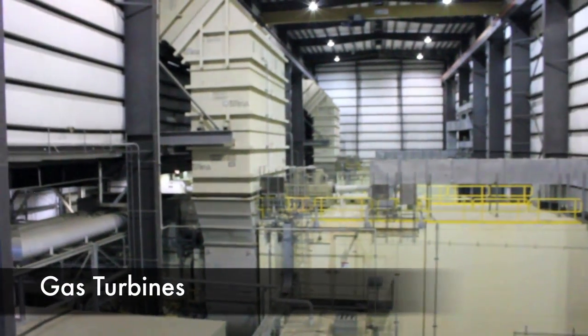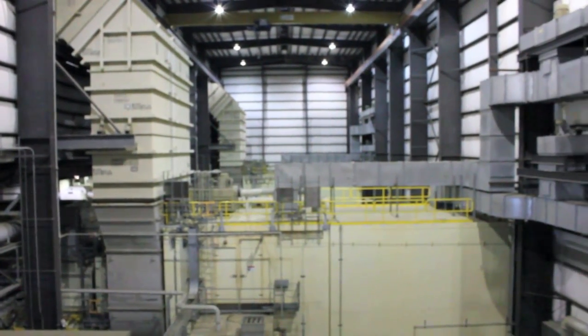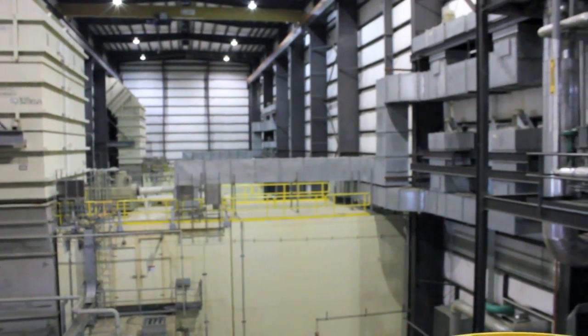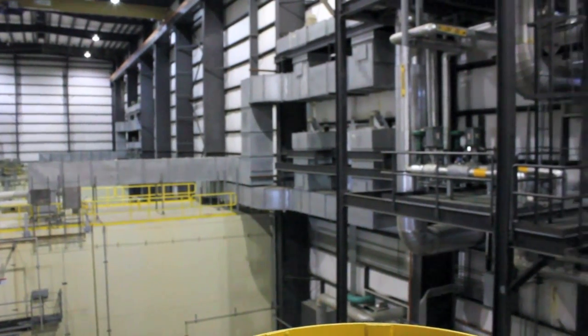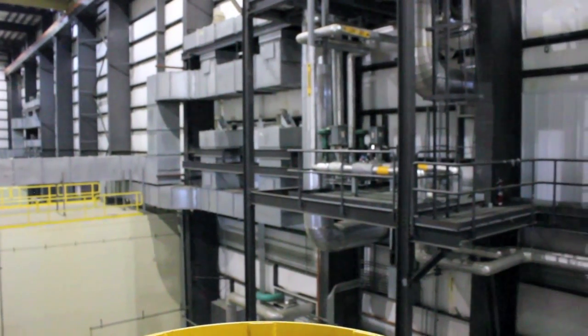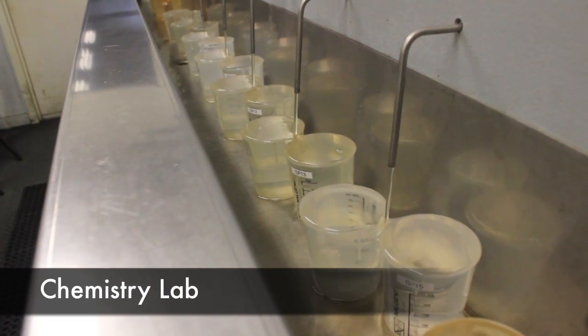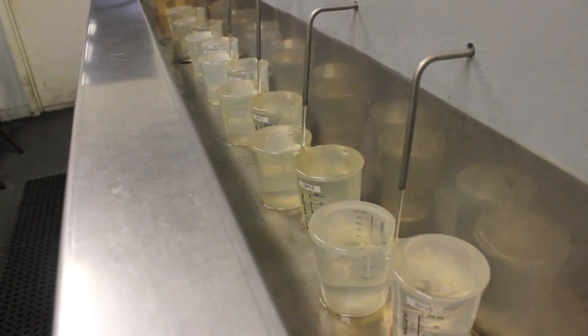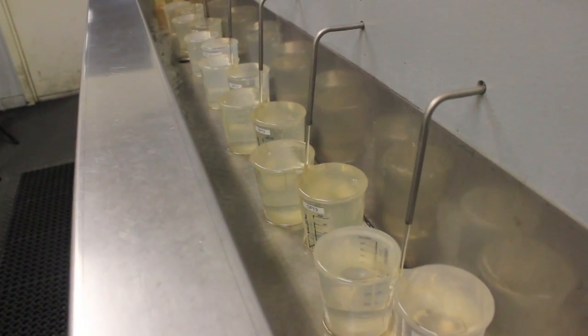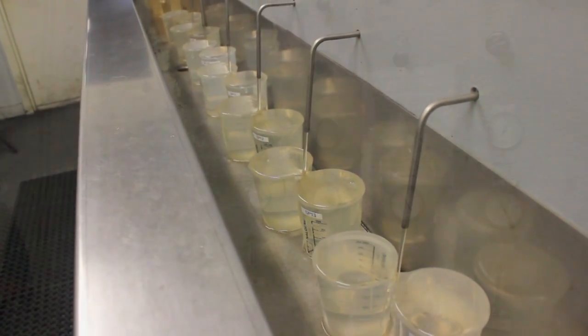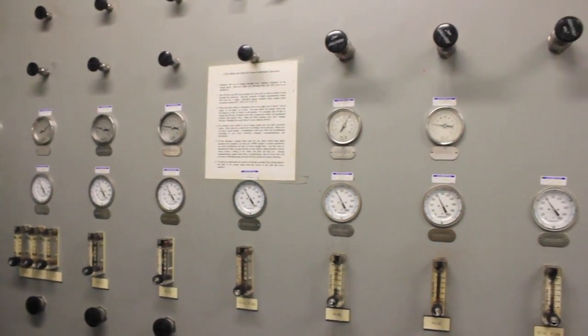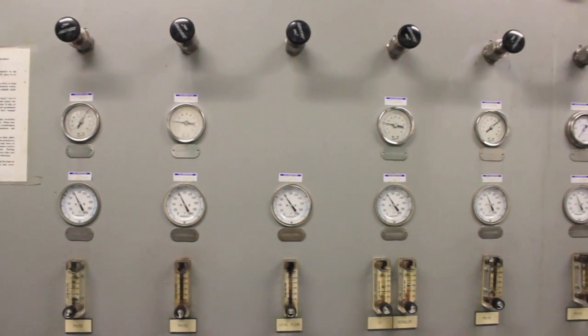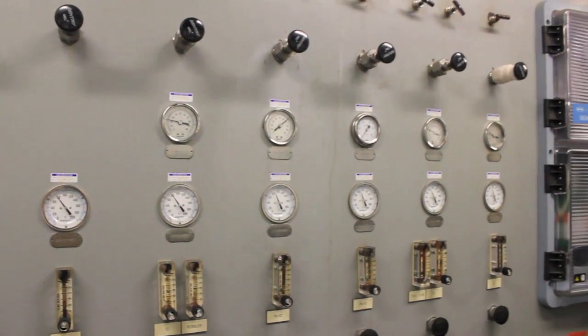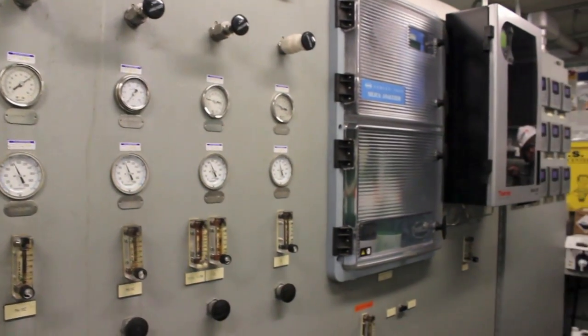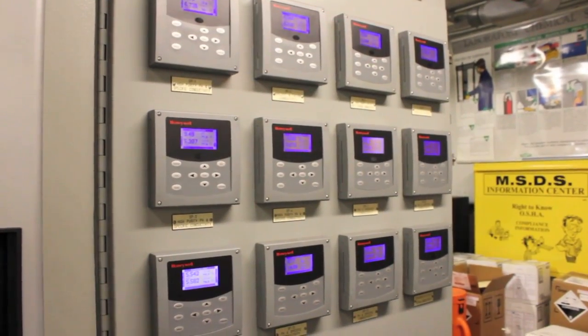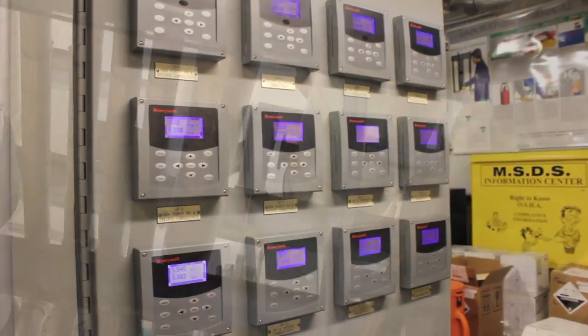We're looking at 2 gas turbines here. Gas turbine 1 is closest to us, gas turbine 2 is behind it. Each of those consumes natural gas to burn and produce power. Each of those generates about 170 megawatts. This is our chemistry lab. We do chemistry twice a day with manual samples that the operators collect. Everything that we do for our water chemistry preserves the life of the power plant, so we are very focused on it. We have online instrumentation that you can see here, as well as the manual samples that the operators do to validate the instruments that are constantly reporting back to the control room.